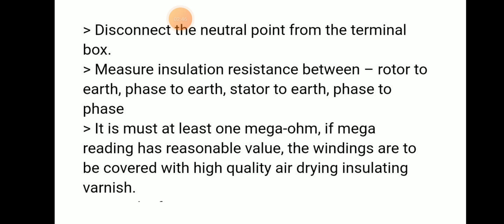We also know the neutral point, we have to disconnect it from the terminal box, and we can measure the insulation resistance using a Megger, between rotor to earth, phase to earth, phase to phase, earth to phase, stator to earth, all combinations we can do. When we test with the Megger, the insulation resistance should be at least 1 mega ohm.